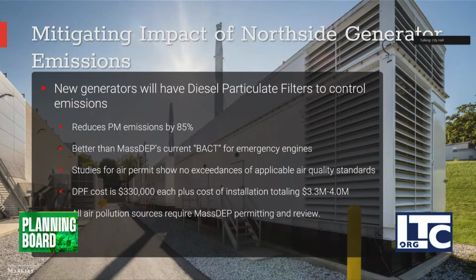These diesel particulate filters cost $330,000 each, not including installation. So for 10 engines, that's $3.3 to $4 million in control technology. And as I said, all the air pollution sources on the facility will require an air permit from DEP.